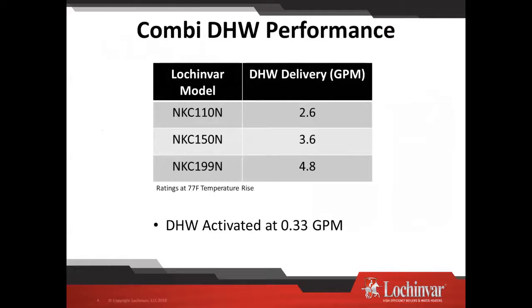The recommendation I do have, if you're putting a combi unit in, to maybe save a later callback, is to put a flow restrictor on the inlet water to the heat exchanger. We'll talk about that when we get to the heat exchanger. Set it for what you're able to deliver. All right.